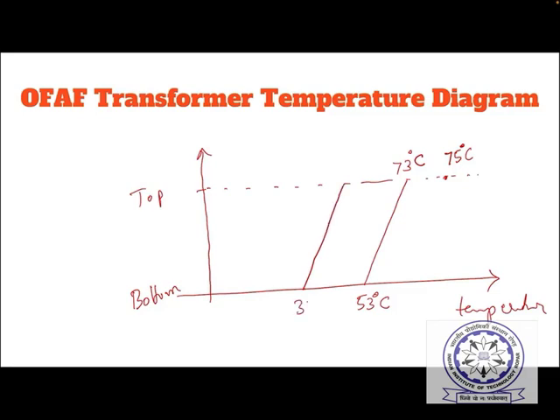So this is 33 degrees centigrade and this is 53 degrees centigrade. This is point C, this is point A. But point B will be cooler, around 41 degrees centigrade only. This is again 20 degrees centigrade. Why is this happening? This is point B. Because most of the oil is getting circulated through the outer portion of the winding.